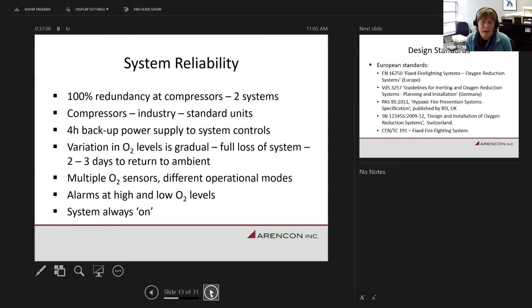Reliability of the system. You have redundancy at the compressors. They cycle. There's on and off. But each compressor is designed so that it can take 100% of the load to maintain the environment. And this is all calculated by the supplier. They may run the tests, or they'll have the data for setting your ignition threshold and your design concentration. They will size the equipment, the number of compressors, the number of nitrogen generators, to be able to maintain that environment in the space. They factor in the number of openings into the space, the temperature, the conditions of the environment, prevailing winds.